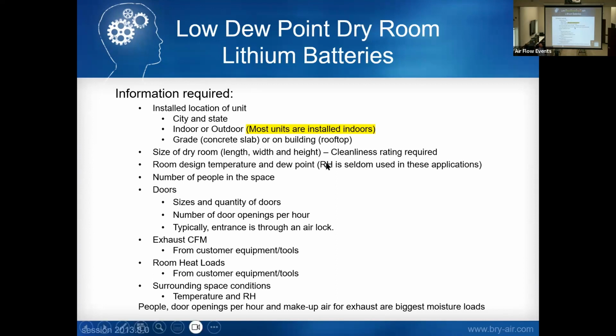So, a little different requirements. Actually, they're not as extensive in terms of figuring out the size of equipment. From an application engineering standpoint, I could do probably 10 of these projects as fast as I could do one regular project, because the data we need is so minimal. You're basically looking at the volume of the room, number of people, door openings per hour, exhaust CFM, heat loads for customer equipment, and the surrounding space. That's it. You don't have re-infiltration because these rooms have to be sealed, from supply ductwork and return ductwork all the way to the rooms. These are zero-leakage type rooms, so they're sealed and you don't deal with infiltration.